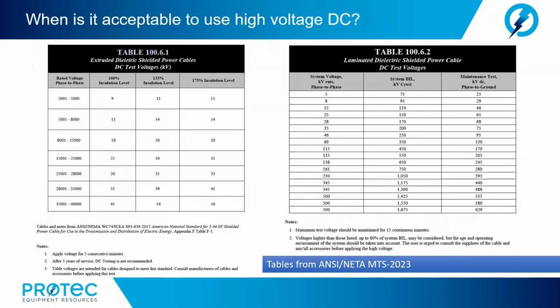Now, since laminated dielectric shielded power cables age differently from extruded dielectrics, the laminated cables do not experience the ill effects of high voltage DC, and they can be tested with DC at any stage of their life. And again, if we go to the NETA guide, we see the reference of laminated dielectric shielded power cables DC test voltages in table 100.6.2. And we see that the maximum test voltage should be maintained for 15 continuous minutes.